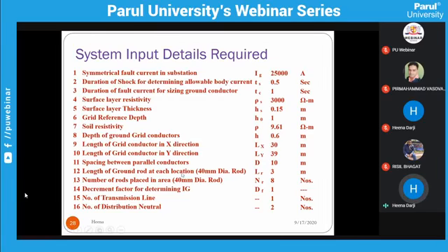Now, length of grid conductor in X direction and Y direction. This depends on your substation. Your substation is 220 kV or 132 kV. All our substations' width and length are different, depending on your kV. So X direction is 30 meter and Y direction is 39 meter.